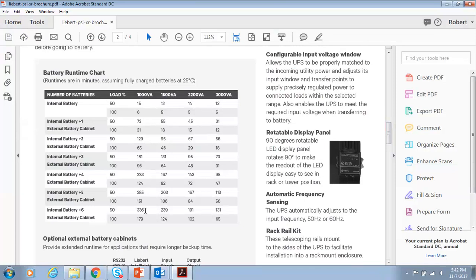So again, people are still kind of directly connecting their gear into these units and running them for a little bit longer. With the larger UPSs, the run times are way down in minutes or sometimes seconds, because they're really only there until an auxiliary power source, most of the time a generator, comes online to replace the utility, versus running everything off the UPS till it runs out of battery.